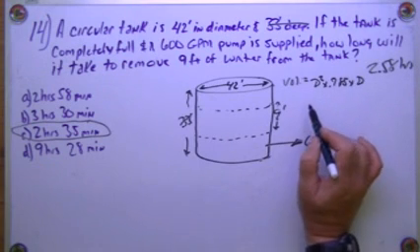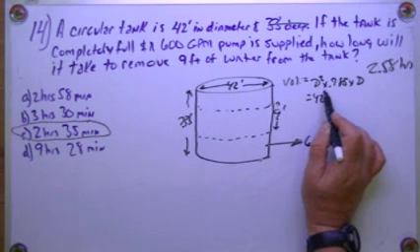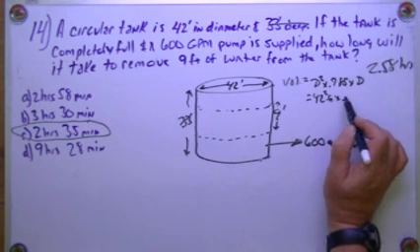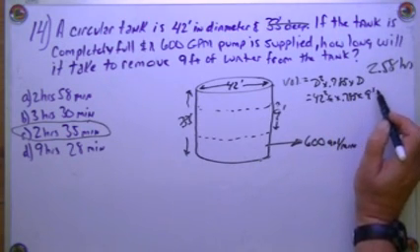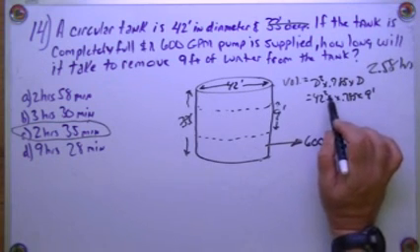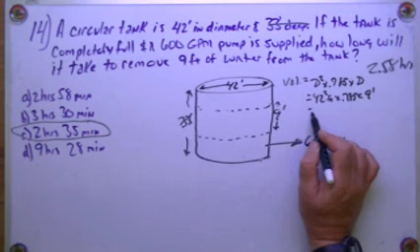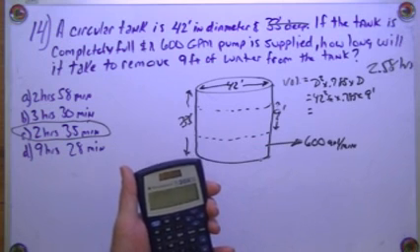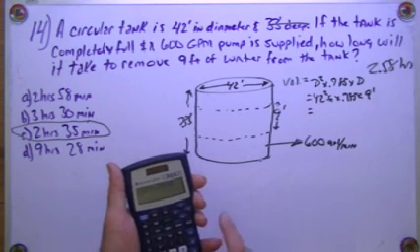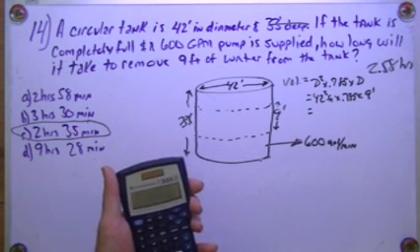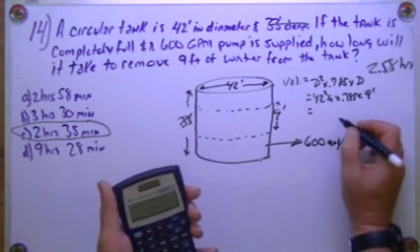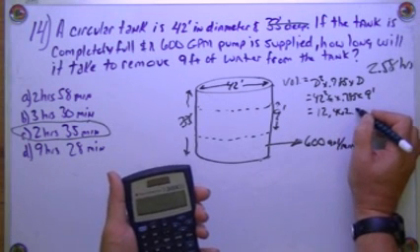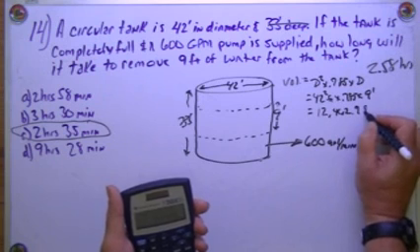So it's going to be diameter squared times 0.785 times the depth. So that's going to equal 42 squared, and that's in feet, times 0.785 times 9 feet. So I've got feet times feet, so it's going to be in cubic feet. So let's do this. 42 squared times 0.785 times 9.